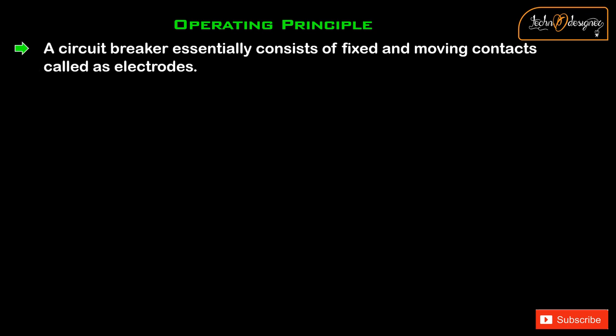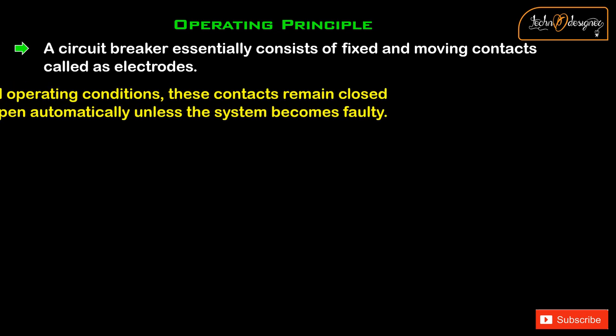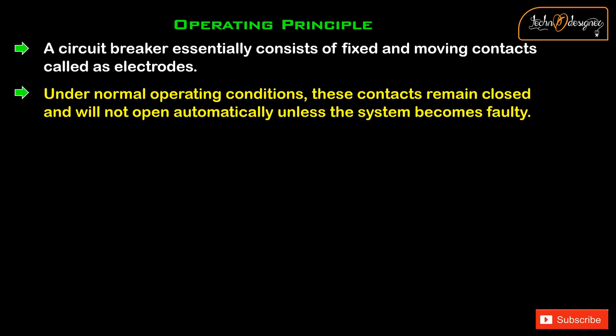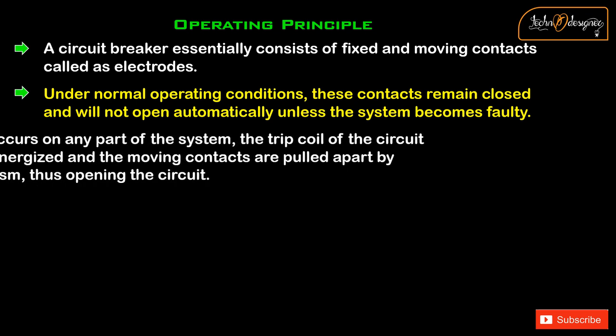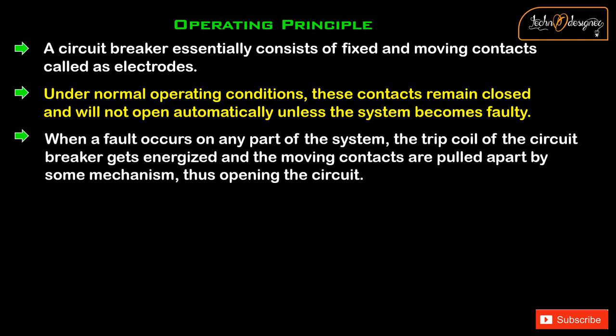Operating principle: A circuit breaker essentially consists of fixed and moving contacts, called electrodes. Under normal operating conditions, these contacts remain closed and will not open automatically unless the system becomes faulty. When a fault occurs on any part of the system, the trip coil of the circuit breaker gets energized and the moving contacts are pulled apart by some mechanism, thus opening the circuit.